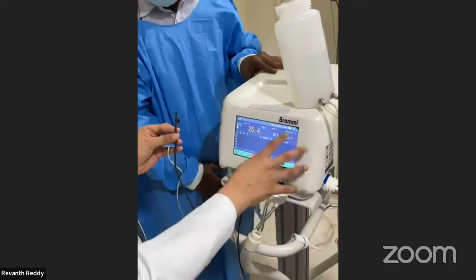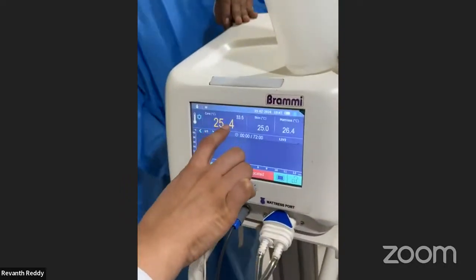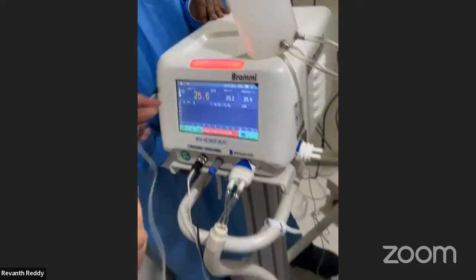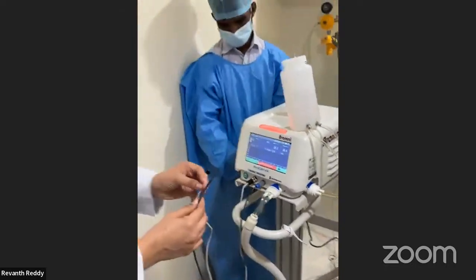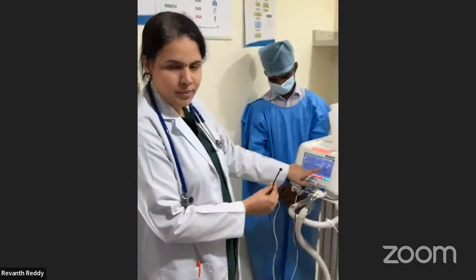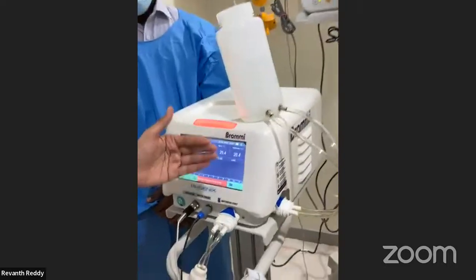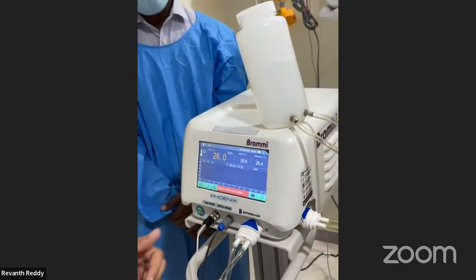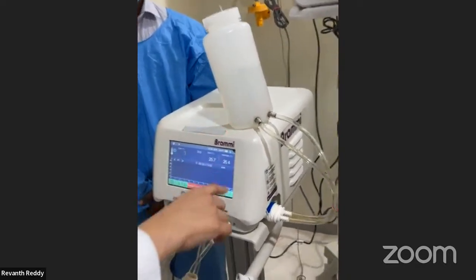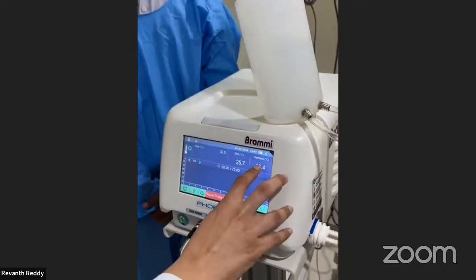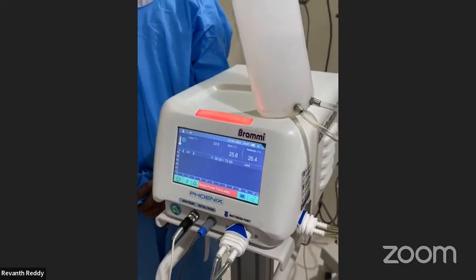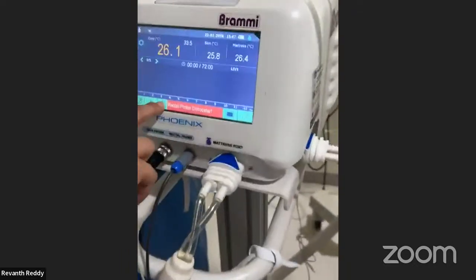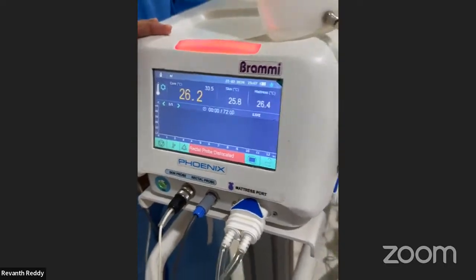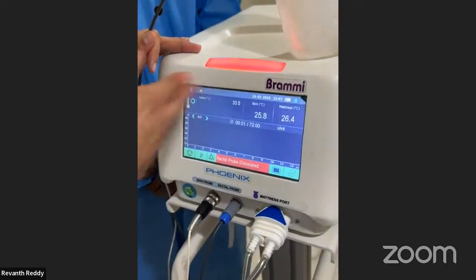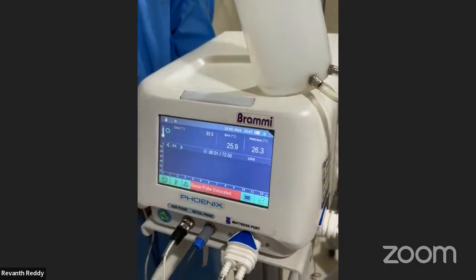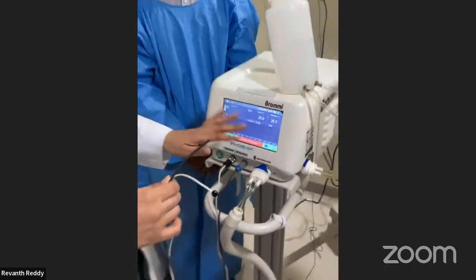So for all practical purposes, we are targeting the core temperature, the rectal temperature. So this is a non-mutable alarm. Since it is out of range now, it is actually continuously alarmed. And concurrently, you'll also be getting the skin temperature, but that is not the one that is used for the servo control mechanism. It also displays the mattress temperature. As of now, it is at 26.4 degrees Celsius. So there are some alarms which even if you press mute, it will not get muted. For example, the rectal probe dislocation, or the core temperature that is out of range. So these are non-mutable alarms. So this is quite a user-friendly interface.